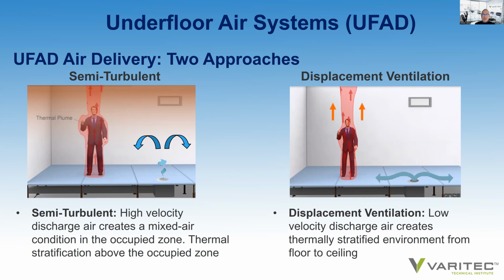The other solution is displacement ventilation. It's another UFAD strategy. Air is ejected into the space at low velocity and horizontally across the floor to create a fully thermally stratified environment from the floor up through to the ceiling or to the deck. These are two strategies. The displacement ventilation strategy offers perhaps better thermal comfort because you have low velocity discharge and reduced risk of cooling ankles, if at all possible. However, because the airflow through them, as I'll demonstrate shortly, is less, you need more of those diffusers. So the first cost is marginally more. The semi-turbulent design injects air at a higher velocity, so you get more airflow, you need fewer diffusers, and it offers a less expensive first cost solution.